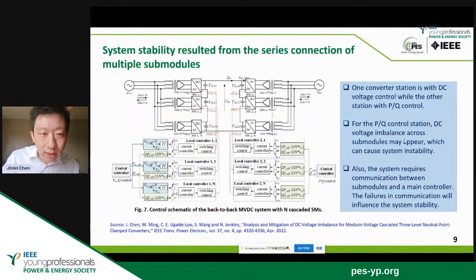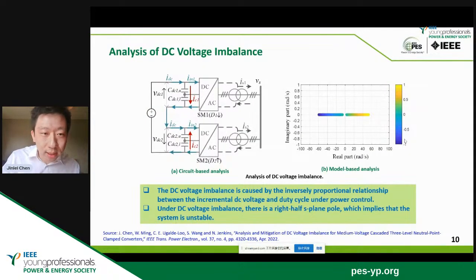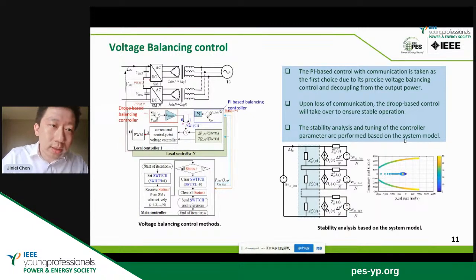To address this challenge, I first analyzed the DC voltage imbalance through circuit-based analysis and model-based analysis. We can see that in the model-based analysis, there is a dominant pole in the right half S-plane, which implies that the system is unstable. Afterwards, I presented the voltage balance control, combining the methods with communication and without communication.